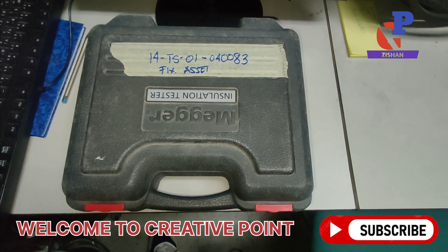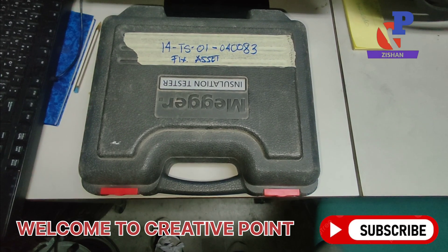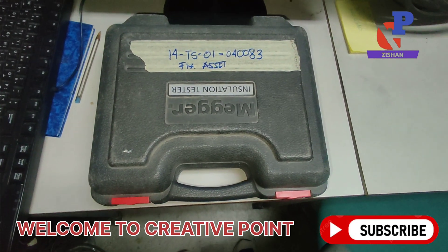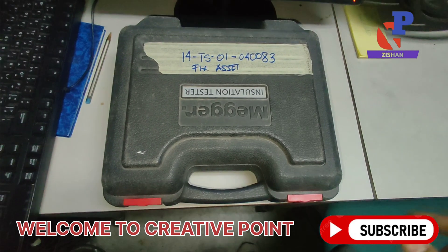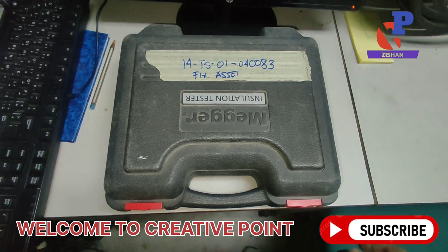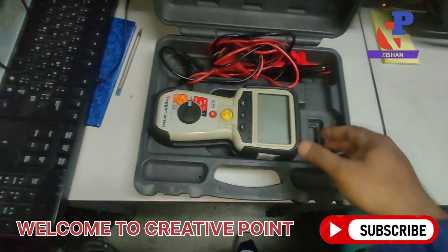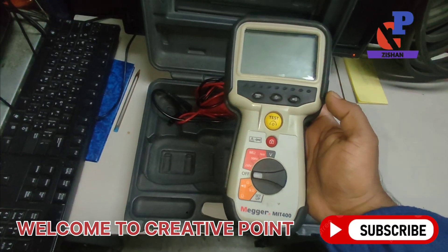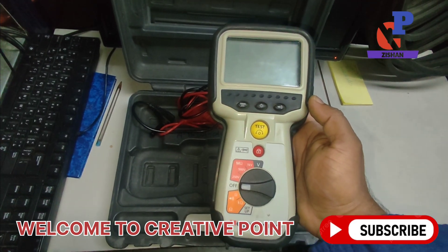Hello everyone, welcome to Creative Point. In this video we are going to perform the megger test of any kind of motor and compressor. This main instrument is called a megger machine, used to check the insulation — whether it has a ground fault or not. The model number of this instrument is MIT 400.